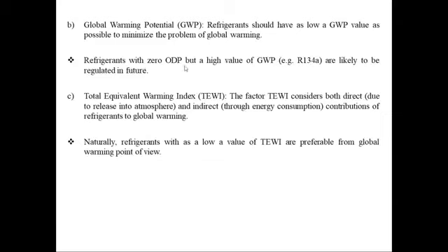Okay. Refrigerants with 0 ODP but a high value of GWP, for example R134a. This is the refrigerant that we are normally using in our country, R134a, and this has 0 ODP, but it has a higher GWP. So that's why this is also in the process of getting phased out.